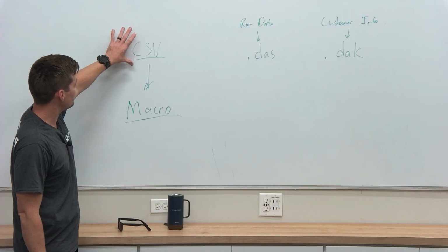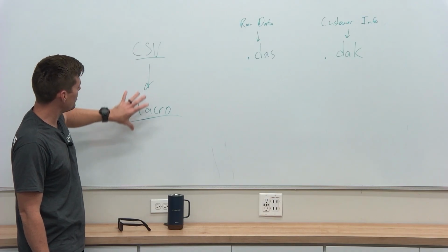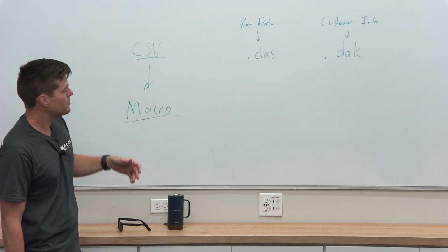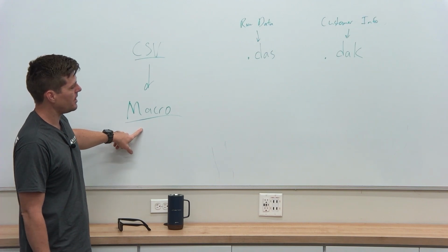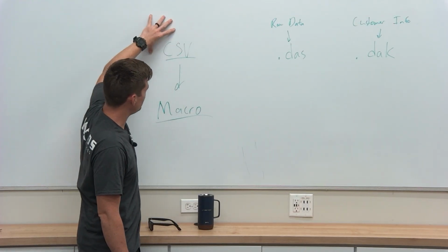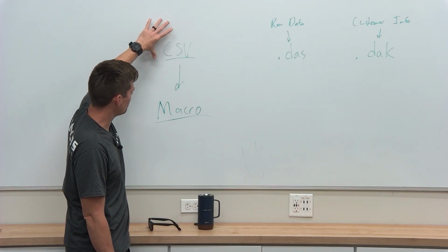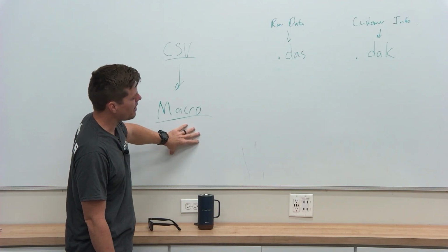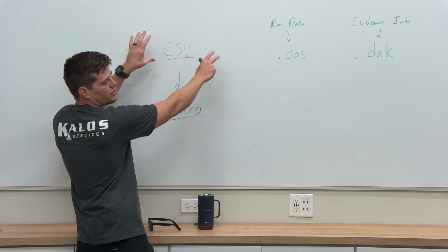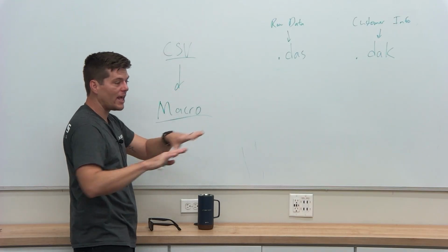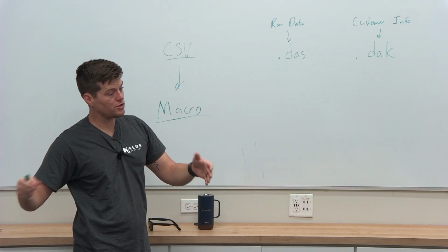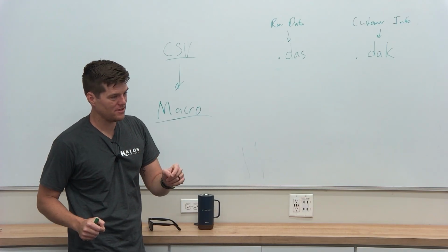And so what it's going to say is, hey, take this information and put it into a format that I can actually easily understand and see. And so the macros that I'm going to give you today take the raw data, exported to a CSV file from Service Checker, and we're going to plug it into a macro. The macro takes all the information here, temperature sensors, pressure sensors, and it will overlay it over a piping diagram that will actually move over time so you can see where the temperature is on the pipes.